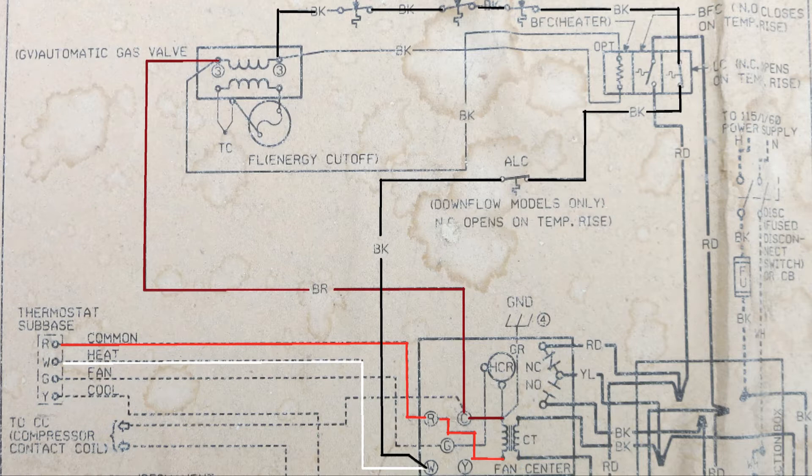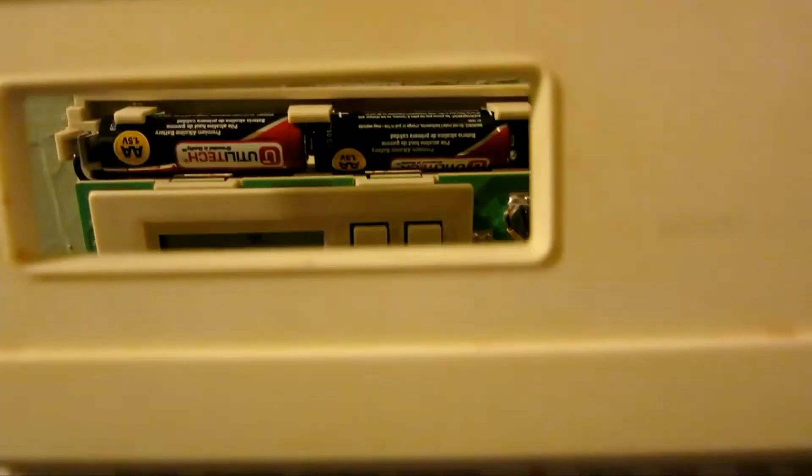As you will see in this video, all of these switches that we check - the over temperature switch, the fan limit switch, and the flame rollout switch - all of them should be short. Because if they're not short, then the gas valve will never receive the 24 volt AC. As you see in this video, as we measure these switches, all of them are short, close to pretty much zero ohms. However, the flame rollout switch was open.